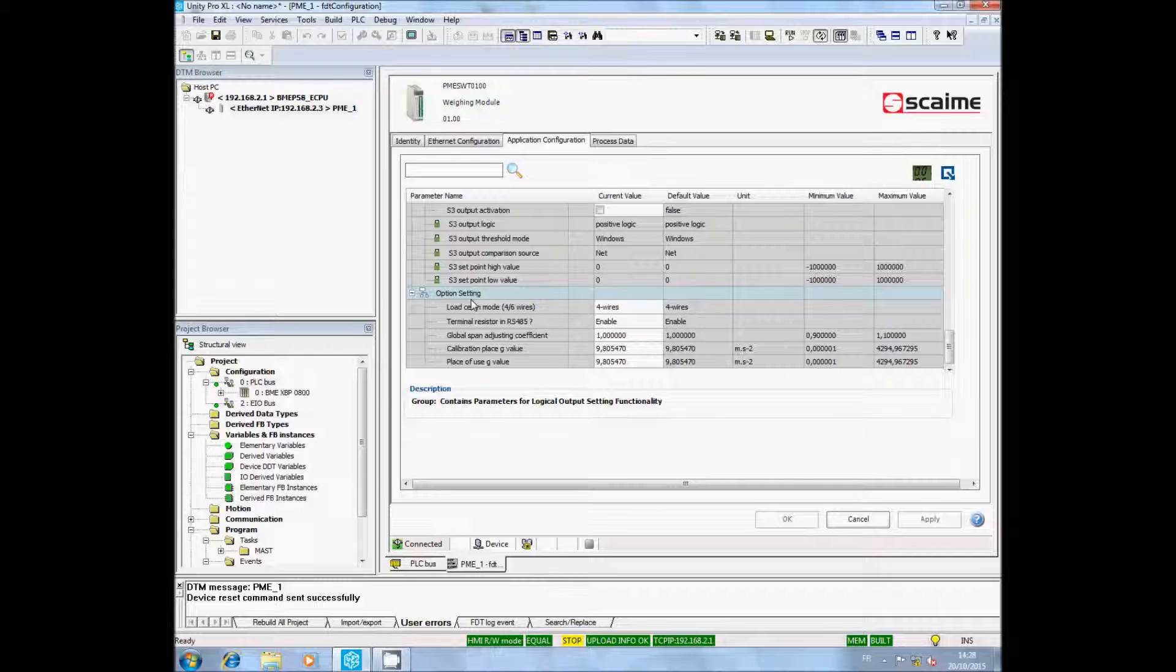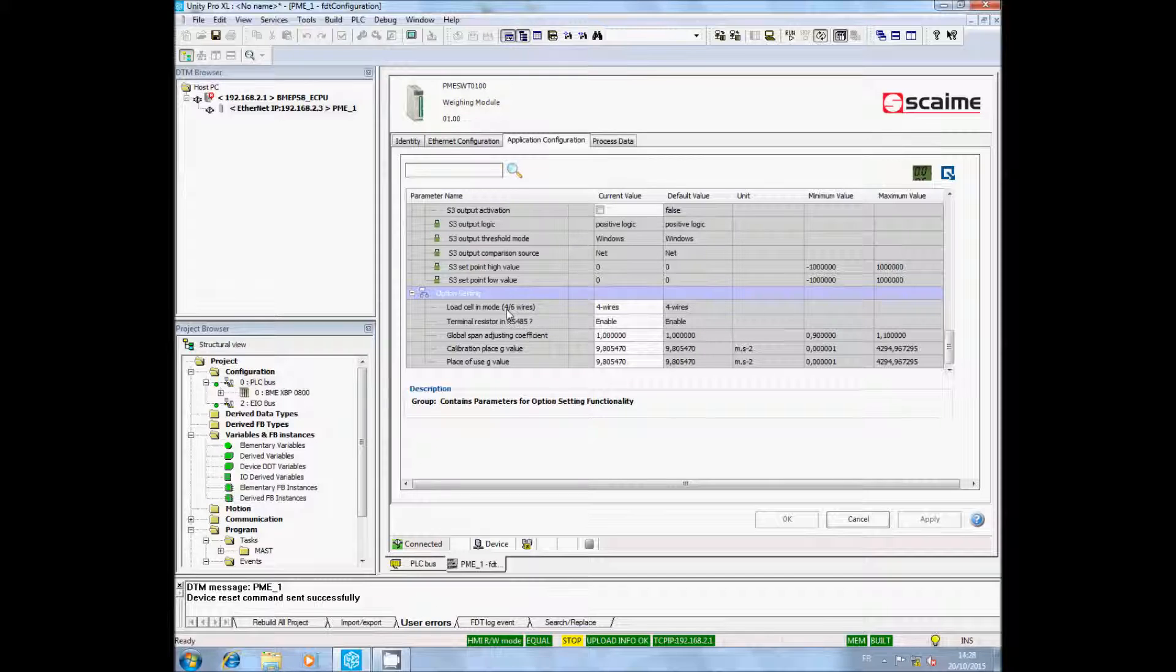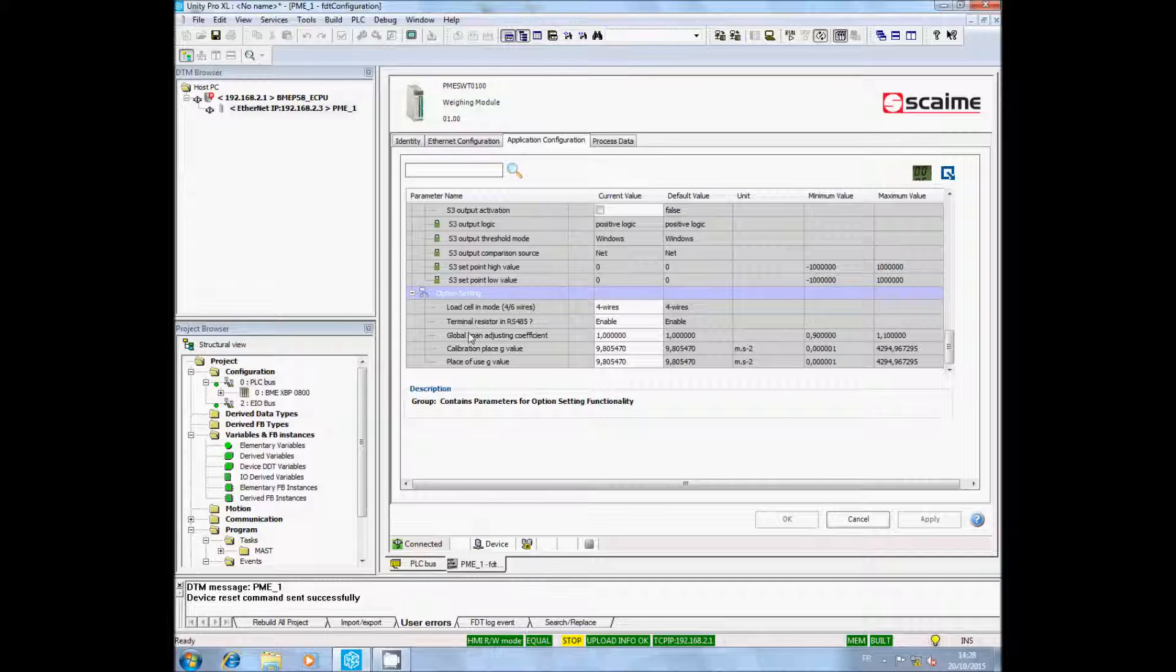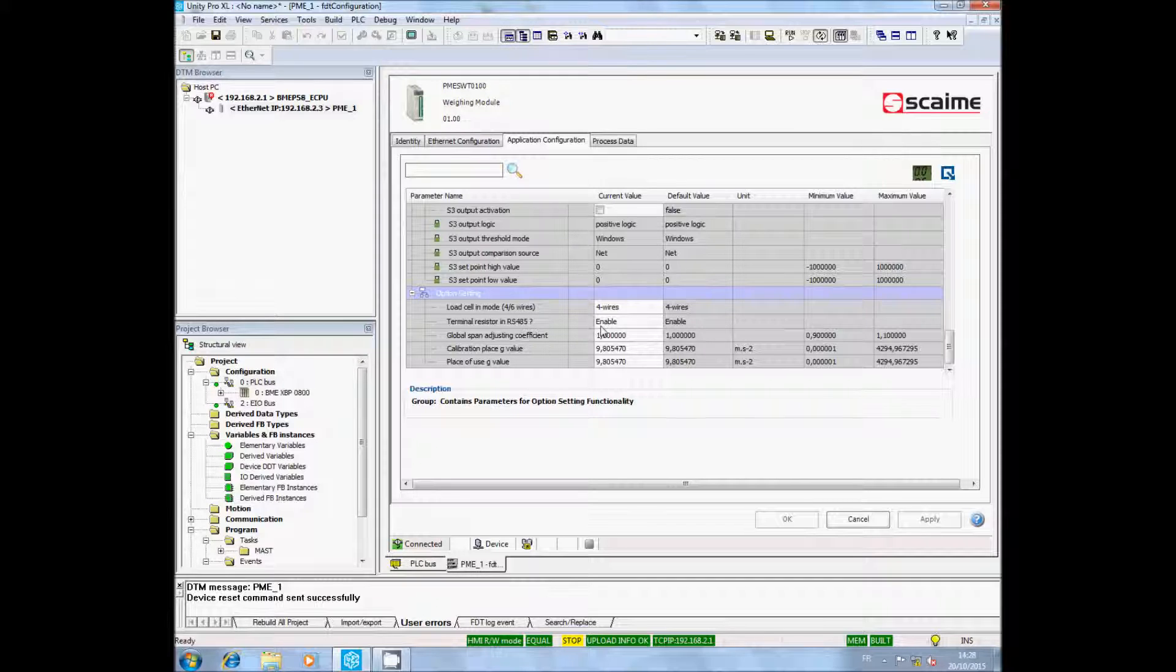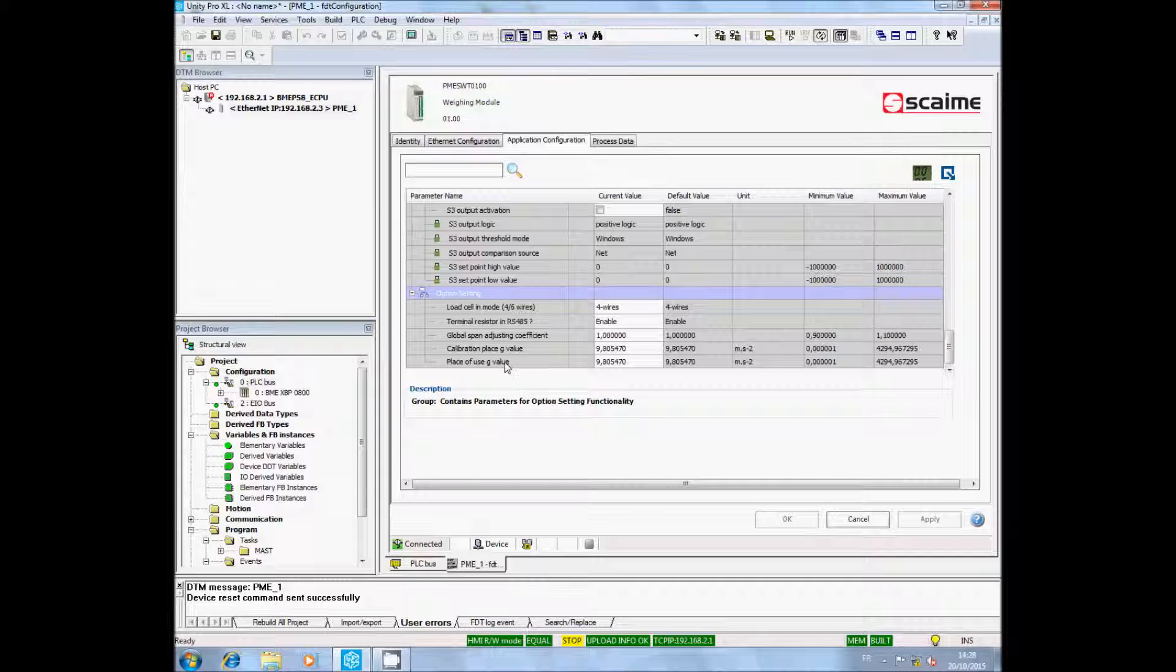You will also access the options settings. In this category, you will configure your load cell type, 4 wires or 6 wires, the terminal resistor of the auxiliary RS-485 port designed for the HMI SWT, the span coefficient or the g values.